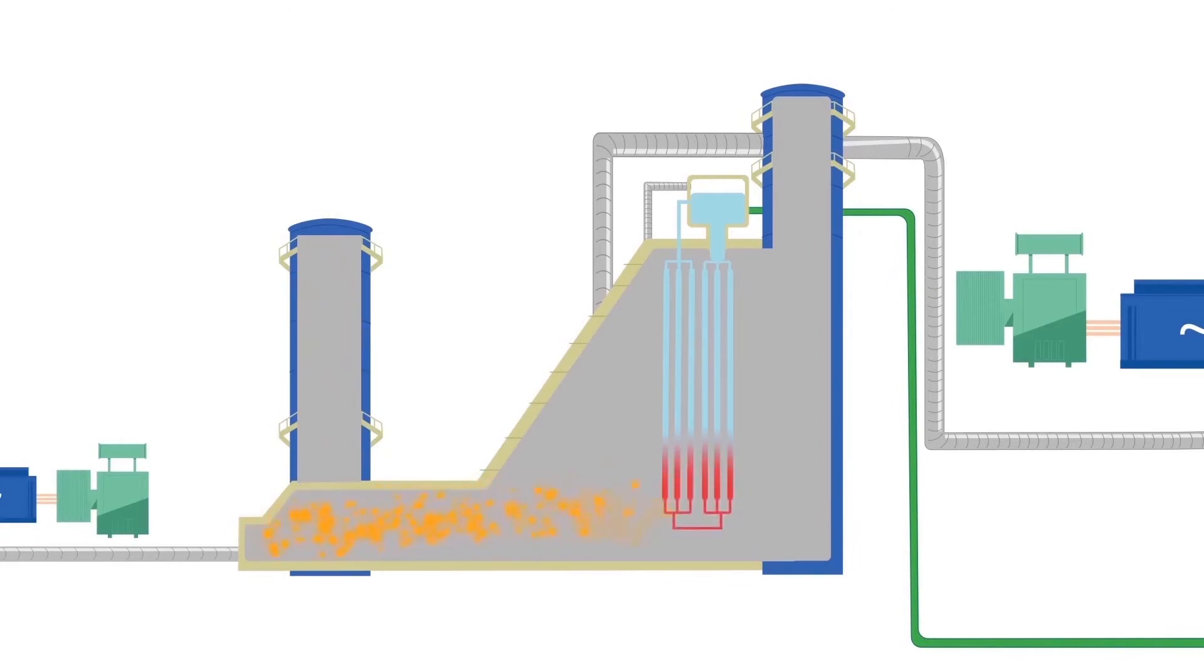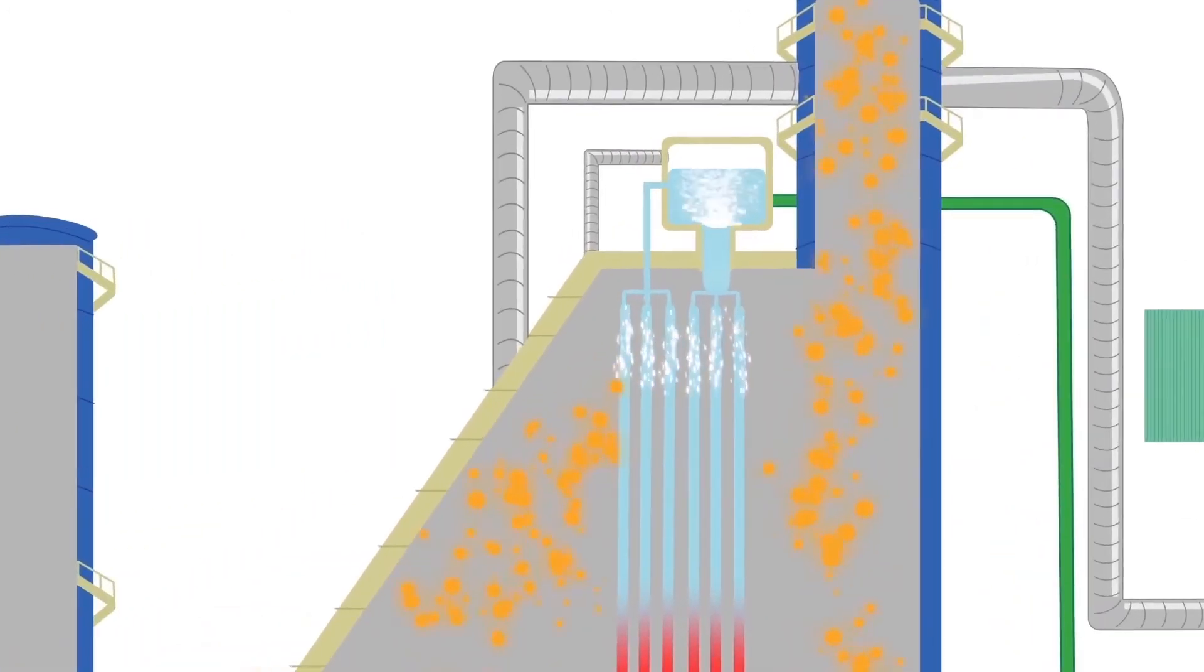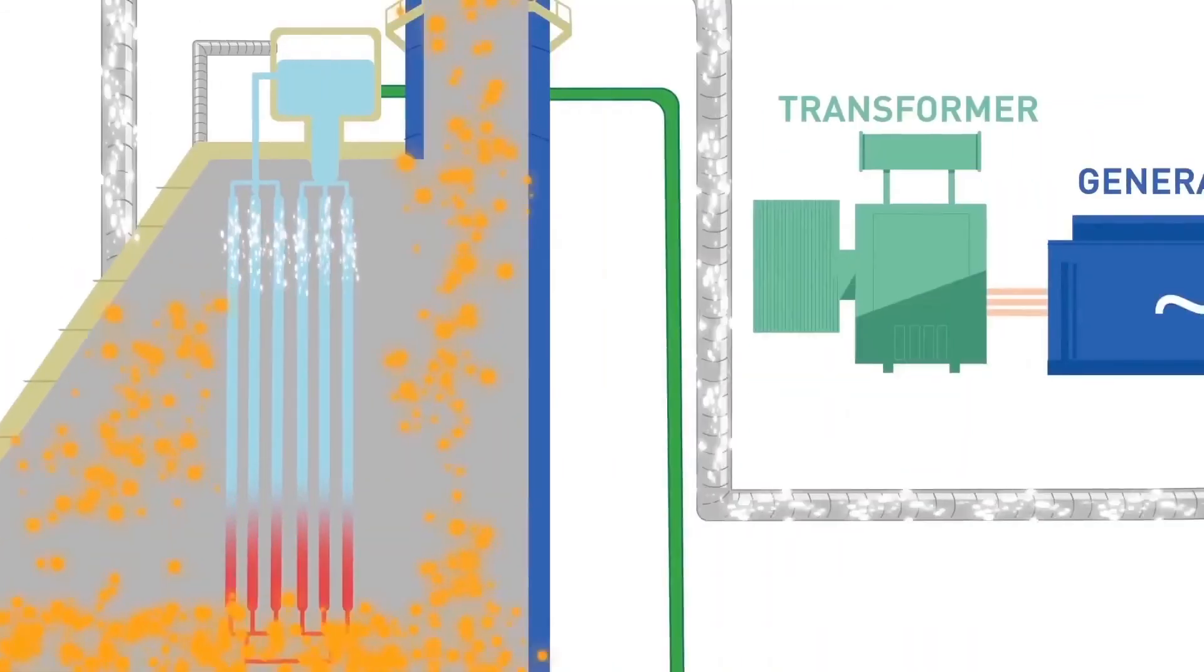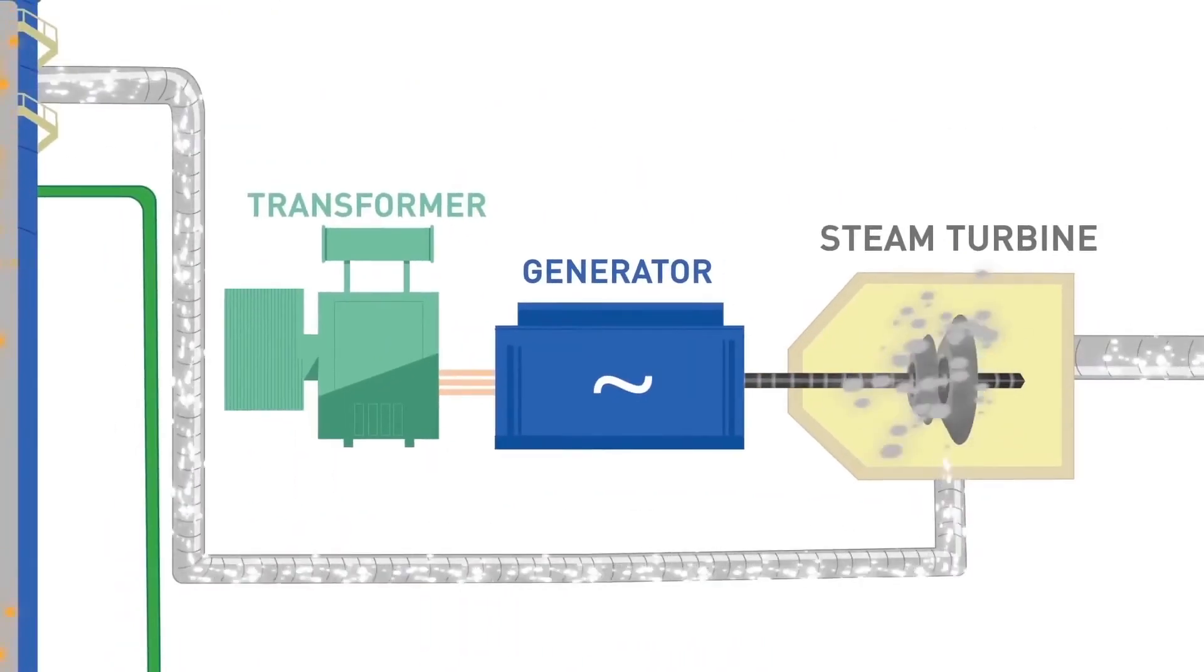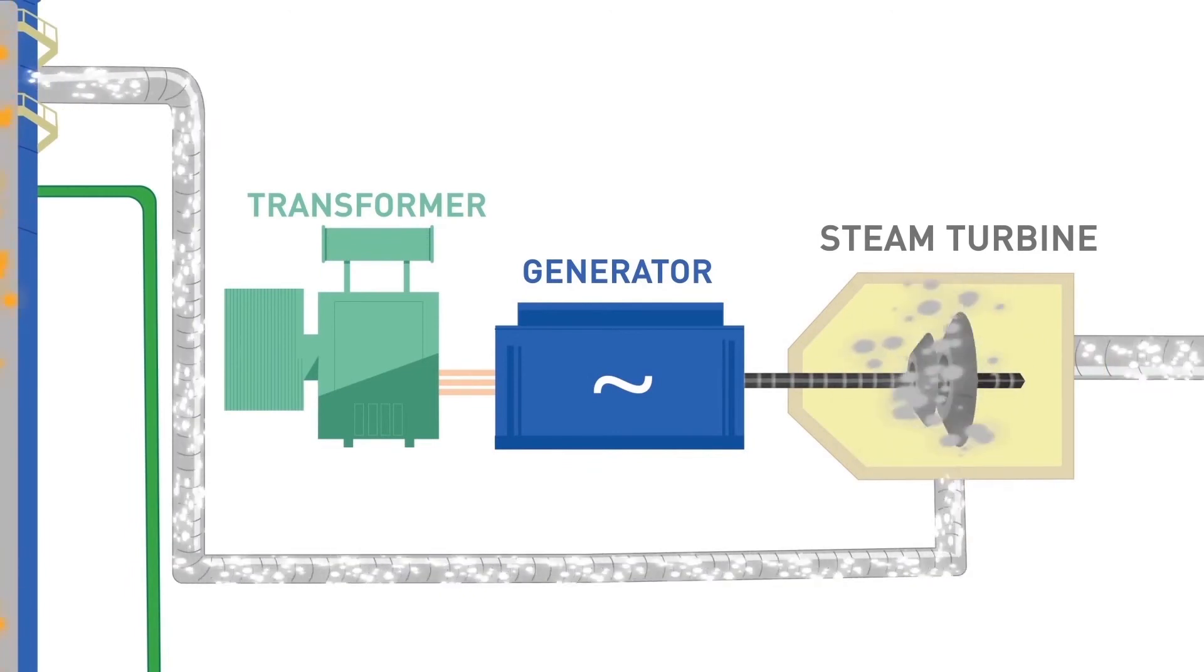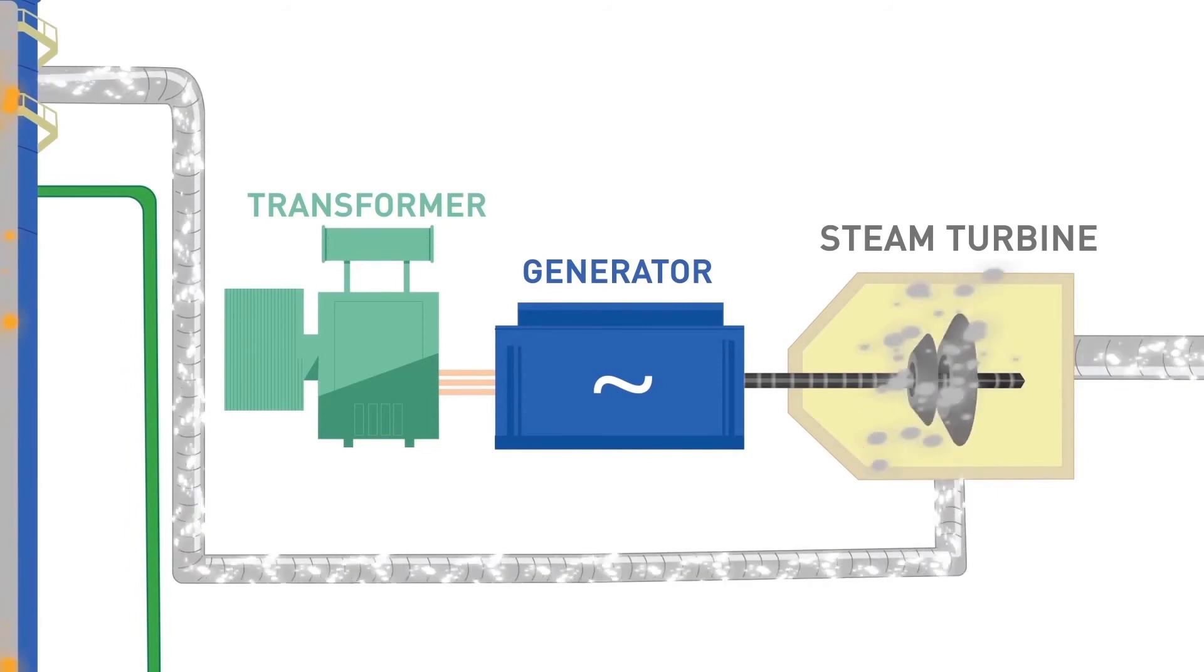Demineralized water contained in boiler drums flows through a series of tubes where it is heated and converted into superheated steam at 103 bars and 540 degrees Celsius. This superheated steam then expands within the steam turbine, causing the turbine shaft, which is connected to the generator, to rotate, thus producing electricity.